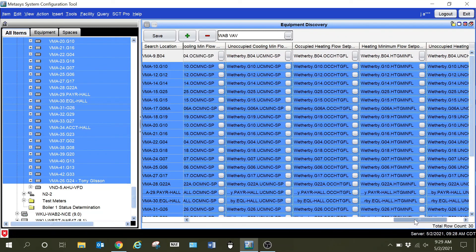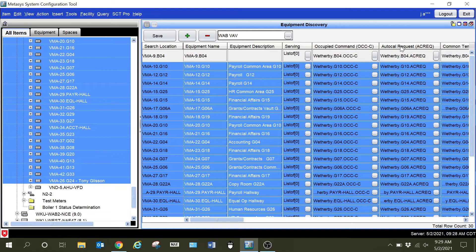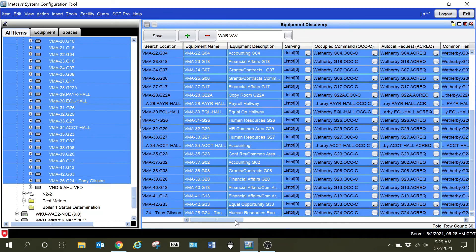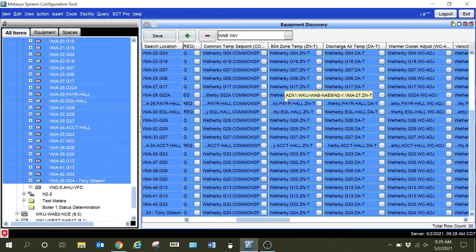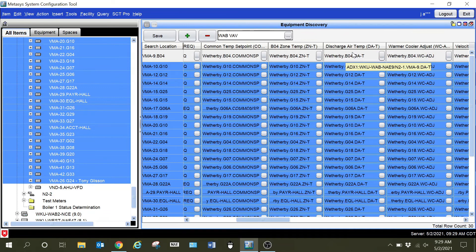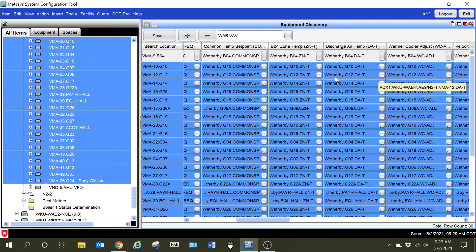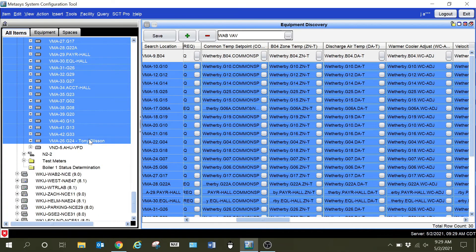I've pulled them all over and it has pulled those individual points for each of these VAVs — just like that. If you wanted to do some rearranging as far as where you want things placed, you can go back in and change that. If you don't have any of these points populated, you can go in and pull in that individual point. In the past, when I tried to pull all of them over at one time without having one already in here first, it left all of these blank and I had to go back and either build them individually or start over — grab the first one, get all the points pulled in, and then grab the rest of them.